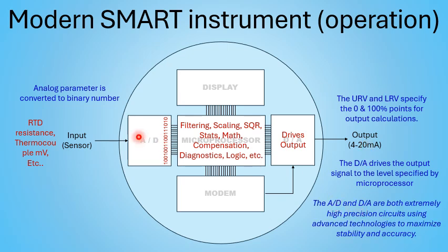The analog to digital and the digital to analog converters nowadays are way more precise, stable, and accurate than they were back in the 80s and 90s. So for that reason alone, these instruments are way more accurate. But the biggest reason is because all of the real math is done inside the microprocessor, and that is extremely accurate by doing it digitally. They typically have that display screen. Not all of them, but some of them will have a display. It's like your M4, M5 option on Rosemount. Other ones have similar options.